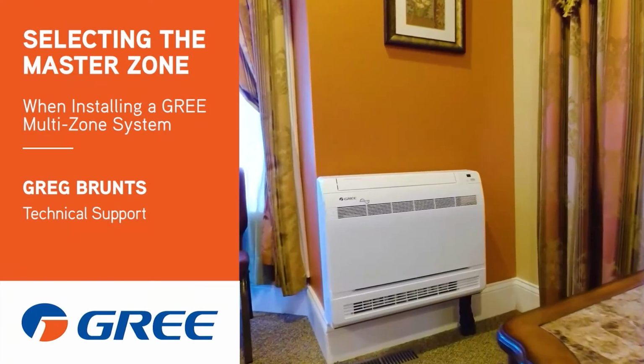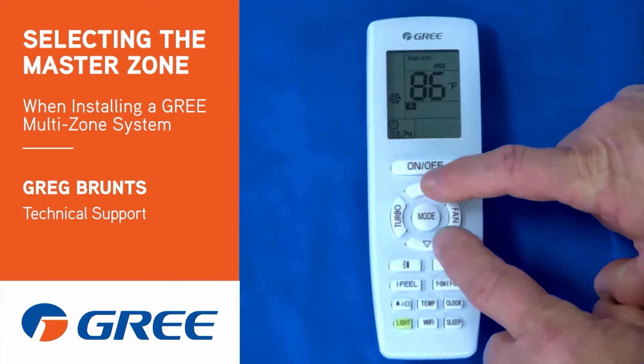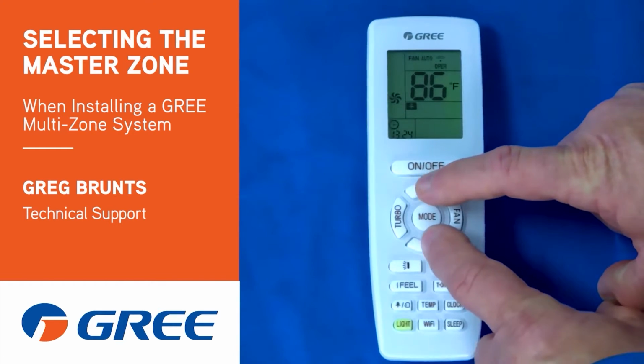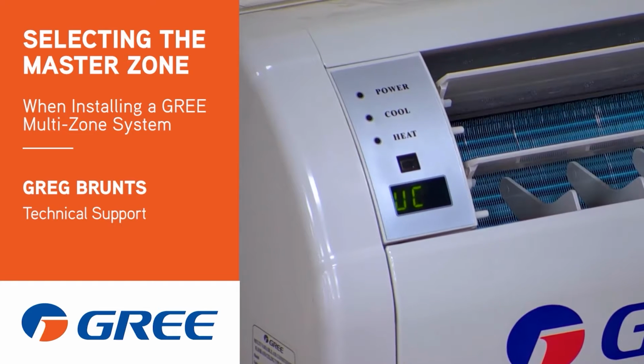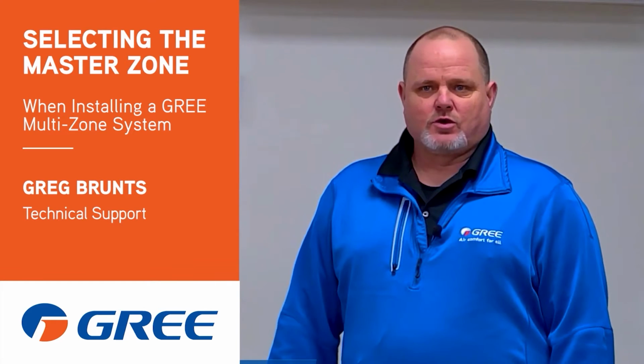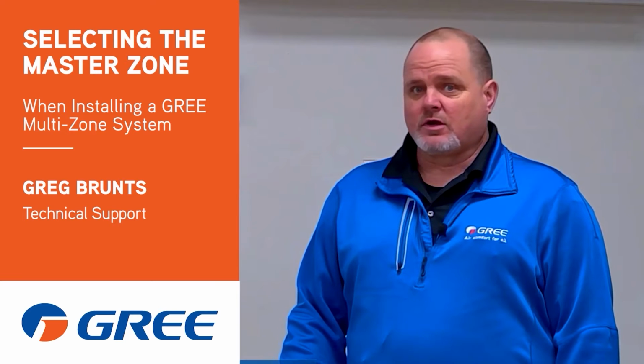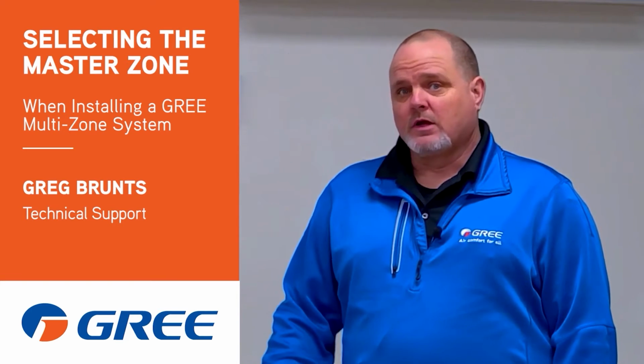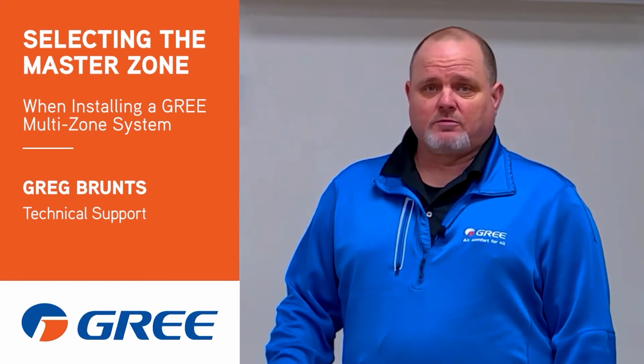I want to show you on the MultiPRO systems, since they auto-address, how, for example on a wall mount, you can change which unit is the master indoor unit. Remember, the master indoor unit is what controls your mode. There is no mode conflict with MultiPRO.